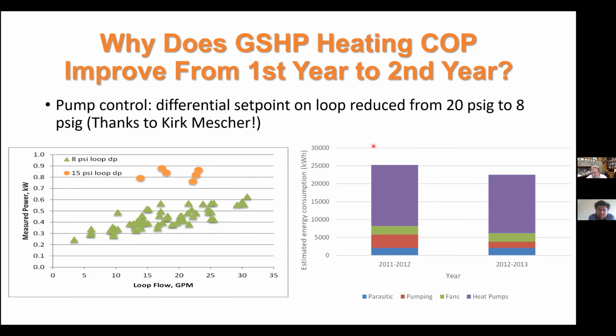We estimated the energy consumption. It's a little hard to see, but the purple here would be the heat pumps themselves, the green would be the fans, and the red is the pumping. You can see it drop quite a bit from 2011-2012 to 2012-2013. So that's one of the reasons why the heating COP went up from one year to the next. I found this quite interesting because this building, being the ASHRAE headquarters, the owner was quite knowledgeable and had really great maintenance staff. It had been commissioned, and still, roughly, the COP going from 3 to 4, or a 33% increase, was sort of left lying on the table. It's something to think about.